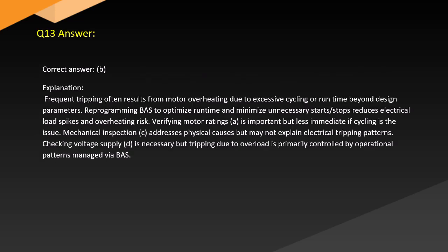Answer. Correct answer. B. Explanation. Frequent tripping often results from motor overheating due to excessive cycling or runtime beyond design parameters. Reprogramming BAS to optimize runtime and minimize unnecessary start-stops reduces electrical load spikes and overheating risk. Verifying motor ratings, A, is important but less immediate if cycling is the issue. Mechanical inspection, C, addresses physical causes, but may not explain tripping patterns. Checking voltage supply, D, is necessary, but tripping due to overload is primarily controlled by operational patterns managed via BAS.